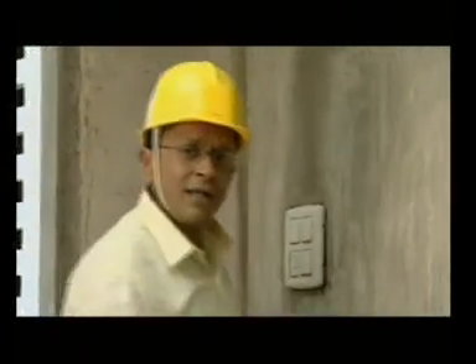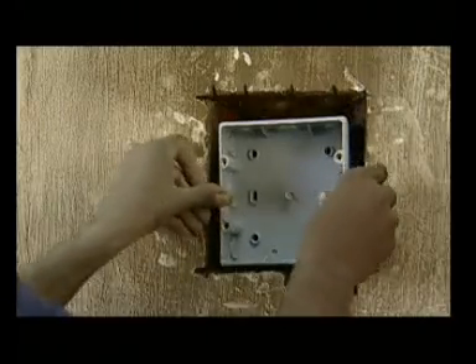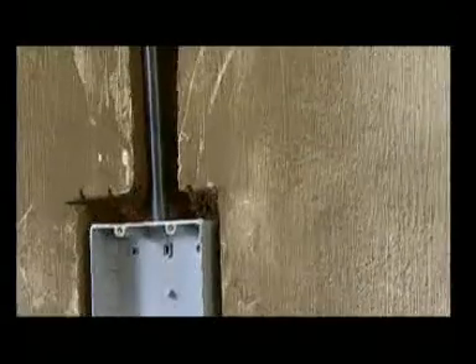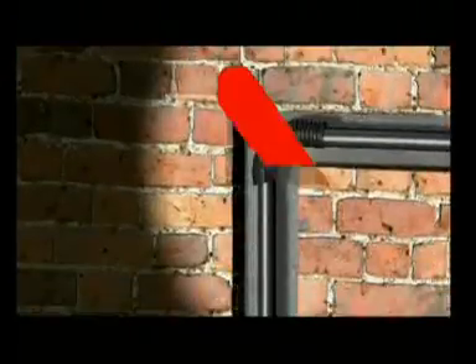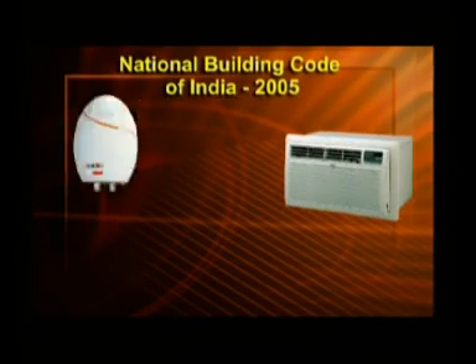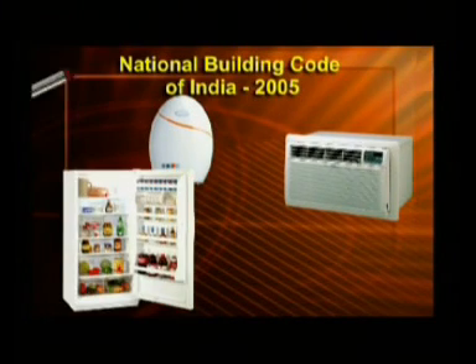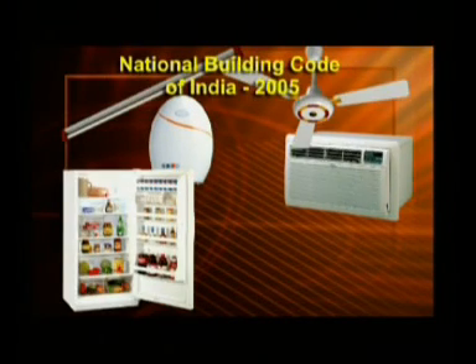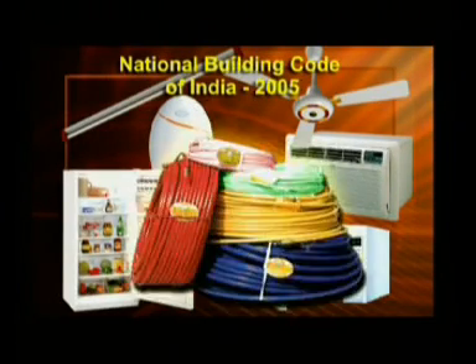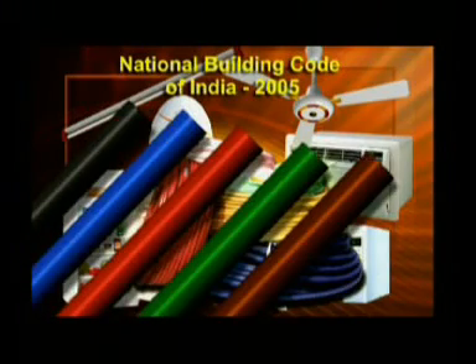To determine the size of the switchboards, you must first decide upon the type of switches you wish to install. Once the size of a switchboard is determined, fix it in the wall first and insert the conduits only after that. While conduiting, take care to avoid places like the toilet sunk and other such places where leakage of water is likely to occur. As per the National Building Code of India 2005, a uniform color code will be applicable for conduits as well as the wires being used in a particular job. This will facilitate in recognizing the wires at the time of repairs and renovation.